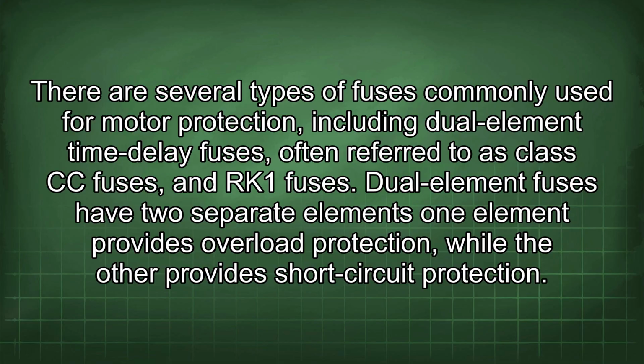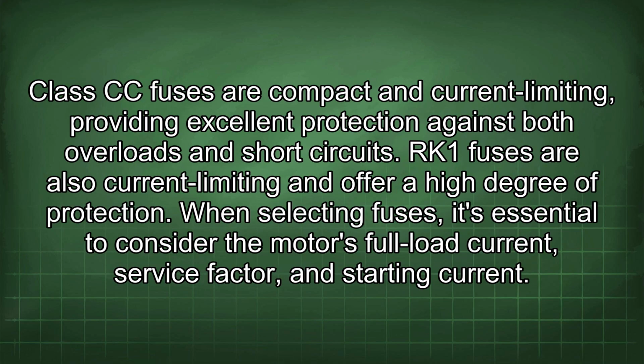Dual-element fuses have two separate elements. One element provides overload protection, while the other provides short-circuit protection. Class CC fuses are compact and current-limiting, providing excellent protection against both overloads and short circuits. RK1 fuses are also current-limiting and offer a high degree of protection.